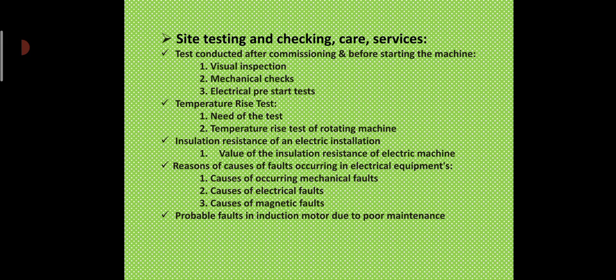Now, reasons or causes of faults occurring in electrical equipment. We studied the causes of faults occurring in electrical equipment by dividing them into three types. Now let us think how this can occur. For example, one case in the category of mechanical faults is an improper bearing. We also saw the effect of this fault on the performance of the machine, but it is necessary to study the causes of the bearing becoming improper.